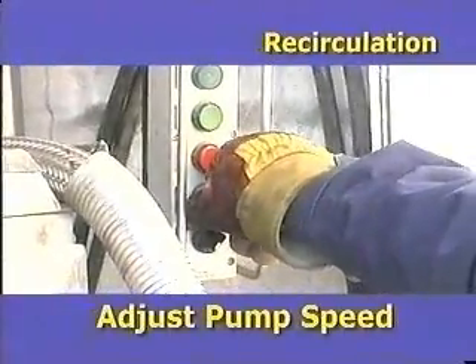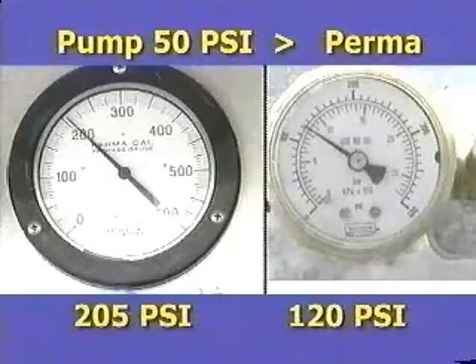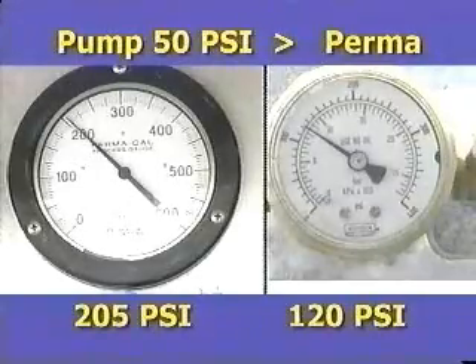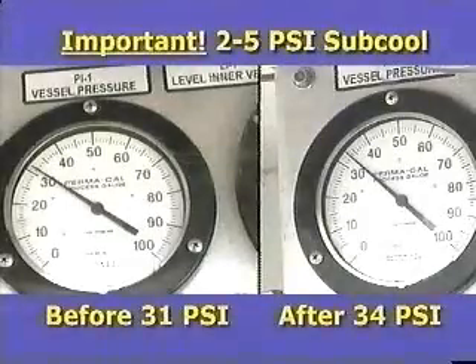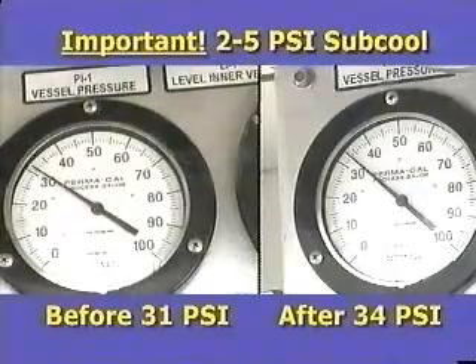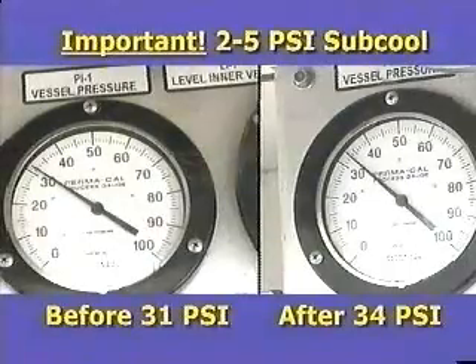Adjust the pump speed until the pressure is at least 50 PSI greater than the PermaCyl pressure. This is required for a successful single hose fill. The maximum delivery pressure for nitrogen is 200 PSI, oxygen 225 PSI, and argon 250 PSI. Review the Orca operating pressure — it must have increased by at least 2 PSI so the liquid is in a sub-cooled state. This is necessary to ensure that two-phase liquid is not present in the pump; otherwise, damage to the pump could occur.